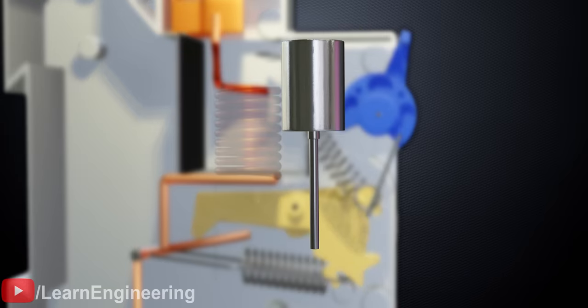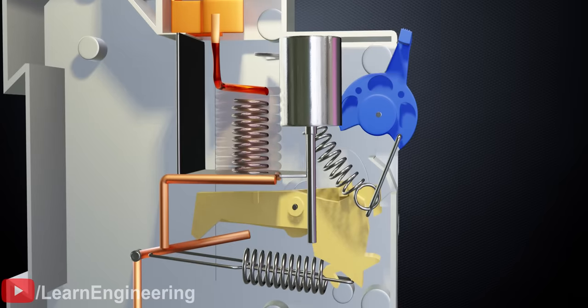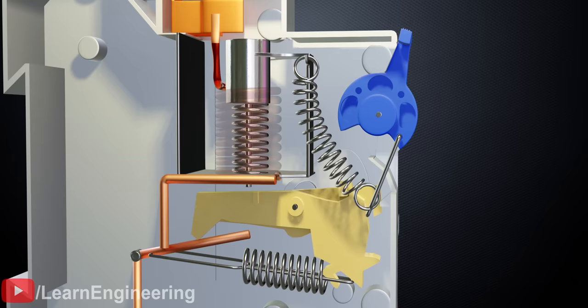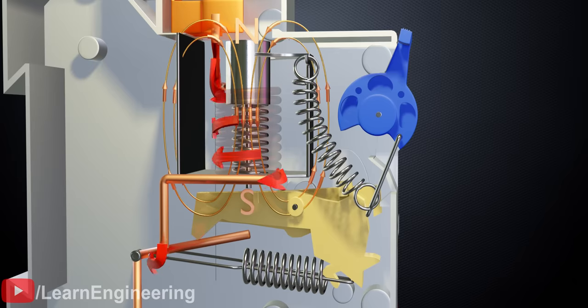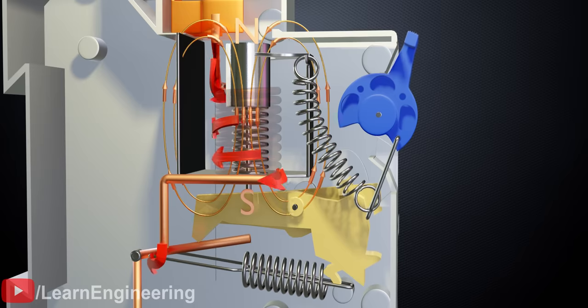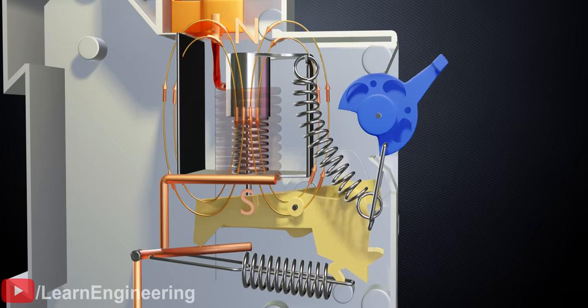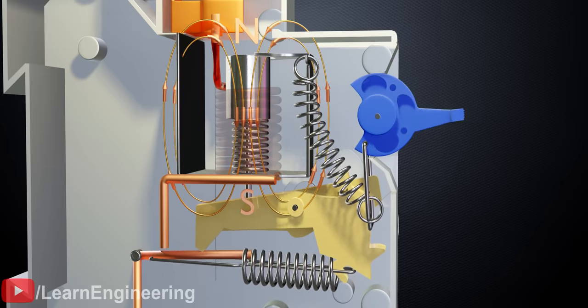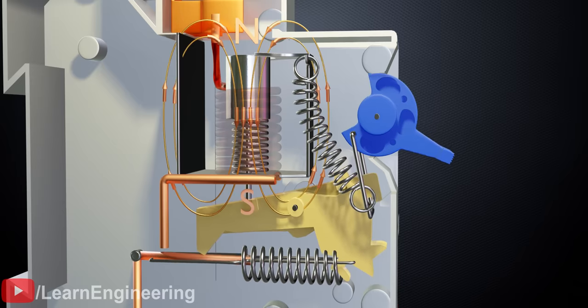An iron cylinder and pin is placed inside this electromagnet on a spring, slightly offset from its center. The strong magnetic field pulls the cylinder downward, thus pushing the pin. This tiny movement of the pin is the input trigger of the mechanism, and it leads to opening the circuit, as we discussed earlier.